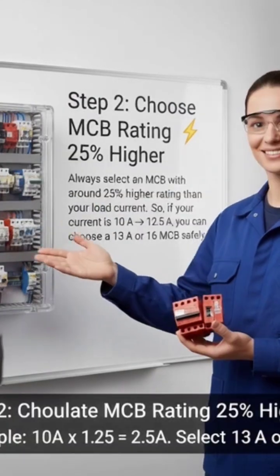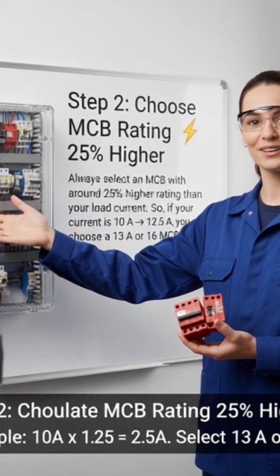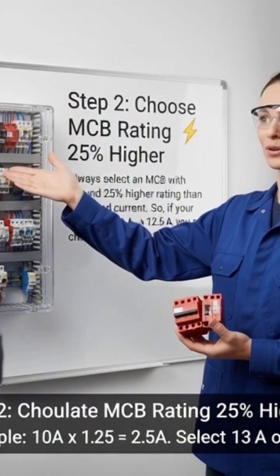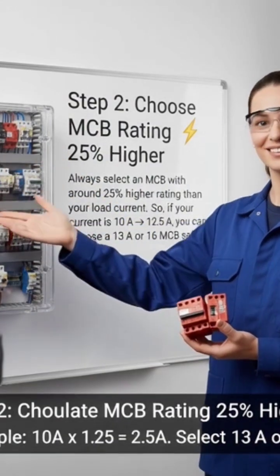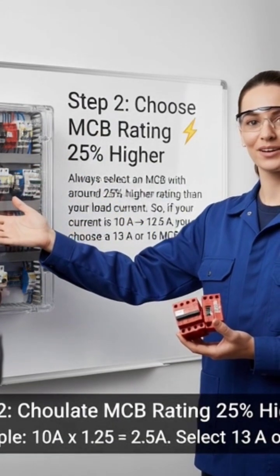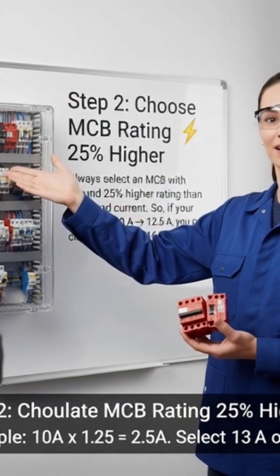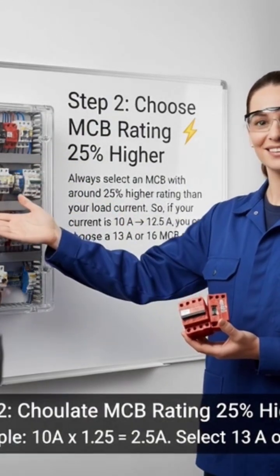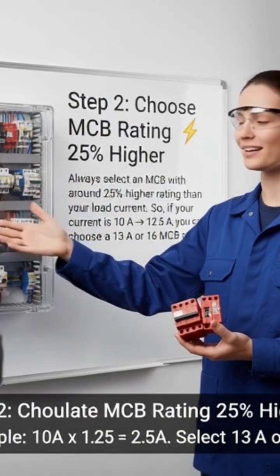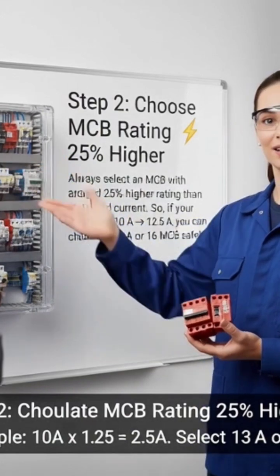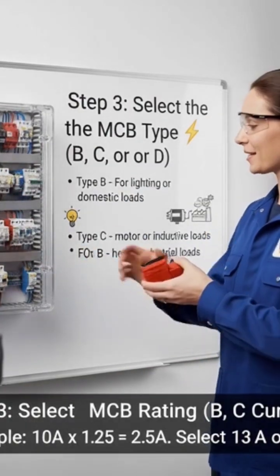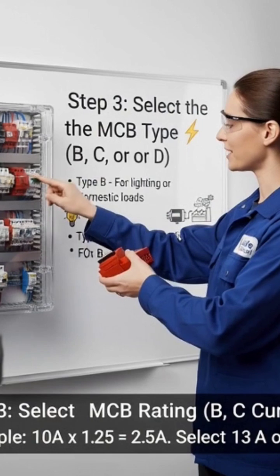Step 2: Choose an MCB rating 25% higher. Always select an MCB with around 25% higher rating than your load current. So if your current is 10A, 10 times 1.25 equals 12.5A, so you can choose a 13A or 16A MCB safely.